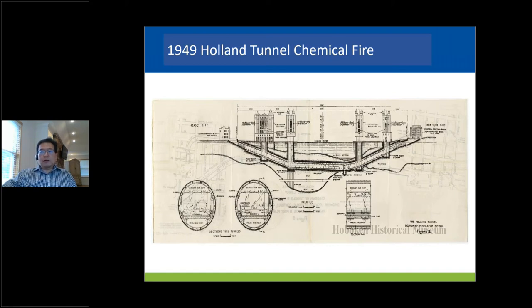Supply air goes into the supply air chamber, and then the air is supplied into the roadway level, where it dilutes with the tailpipe gas. The heated and polluted gas is exhausted out through the top exhaust plenum, and eventually exhausts out through the ventilation building.